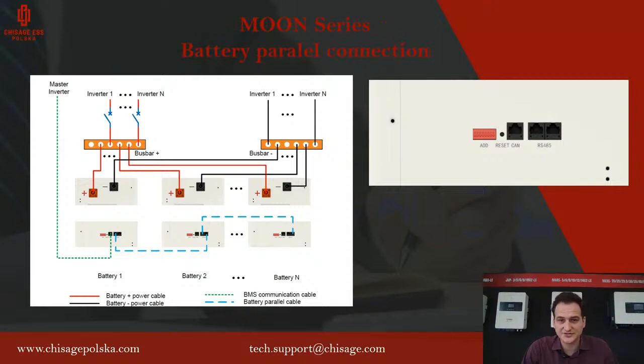For the batteries parallel connection. For the Moon series, we connect the first battery to our inverter. We use this port named CAN on our battery. And then from the first battery to the second battery, we use these RS485 ports. So we go from the first one to the second one, from the second one to the third one, and so on. And then when we connect the power cables in parallel, we have to use a bus bar for the positive and negative power cables to the inverters.